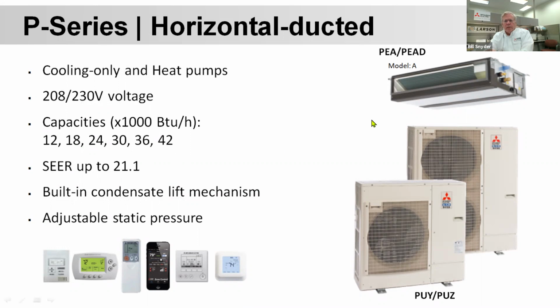Horizontal ducted unit, this PEAD, which you can also use on the MXZ multi-units we talked about. This develops a little bit more static pressure. I think it's 6 or 8/10 of an inch of static. So it's a lot better than the smaller unit we talked about earlier today. So this is the one we use a lot, especially if you're going to put electric heat and some ductwork on, because this one here you can go all the way up to 42,000 BTUs.